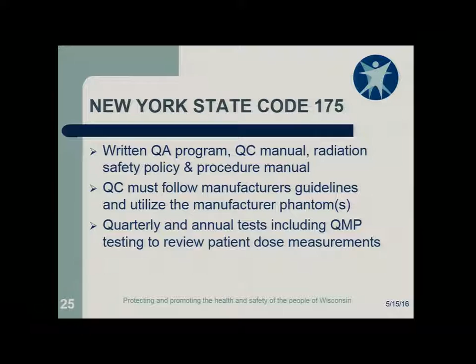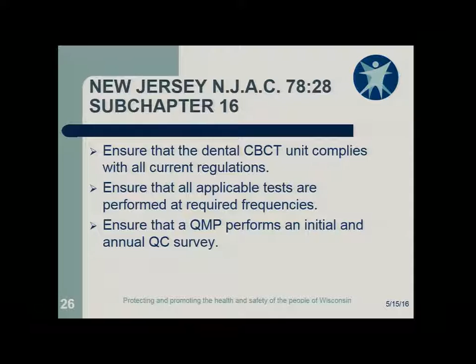New York State Code 175 requires a written QA program, QC manual, radiation safety policy, and procedure manual. QC must follow manufacturer's guidelines and utilize the manufacturer's phantom. Quarterly and annual tests, including QMP tests to review patient dose measurements. New Jersey: ensure that the dental cone beam CT unit complies with all current regulations. Ensure that all applicable tests are performed at required frequencies. Ensure that a qualified medical physicist performs an initial and annual QC survey.